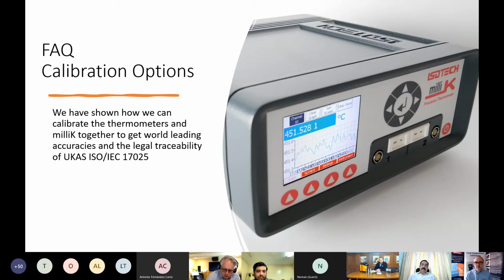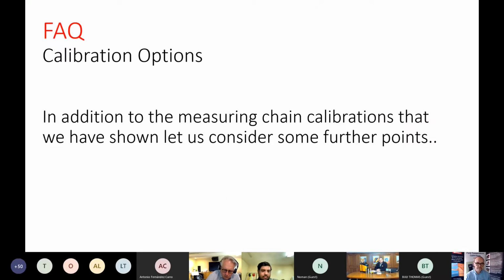So what we've shown so far is how we can calibrate the thermometers and milliK together to get world-leading accuracies and the legal traceability of UKAS ISO IEC 17025. But there are some subtle points that I want to bring out, because in addition to the measuring chain calibration, we need to think about some further points.